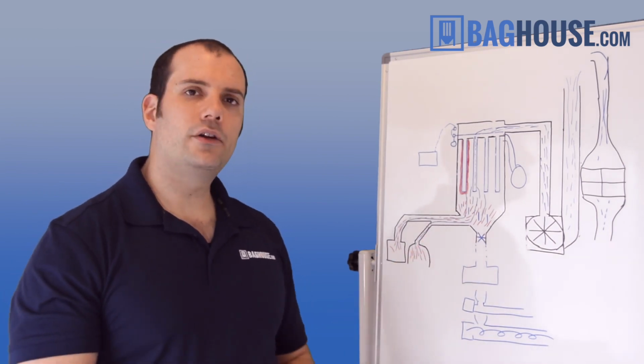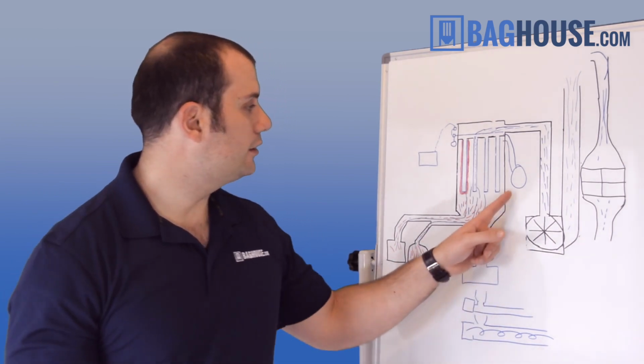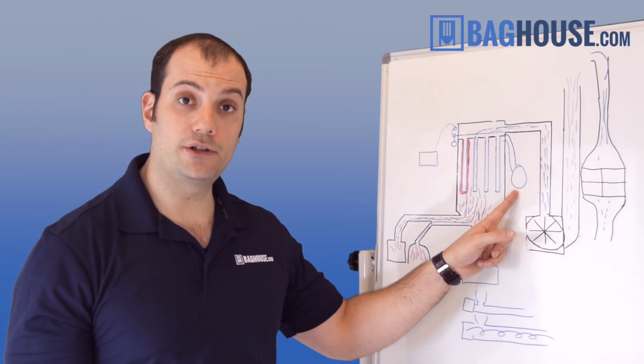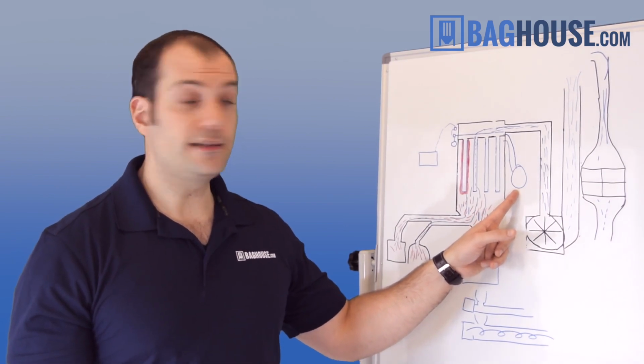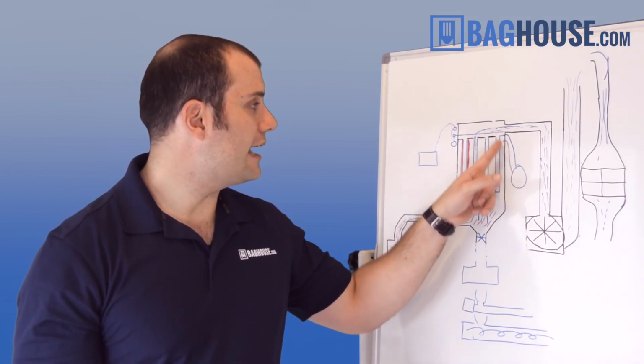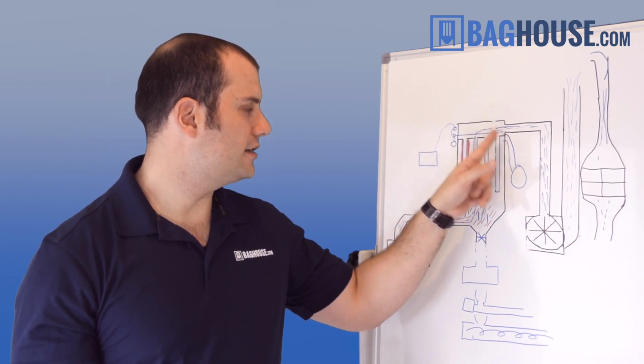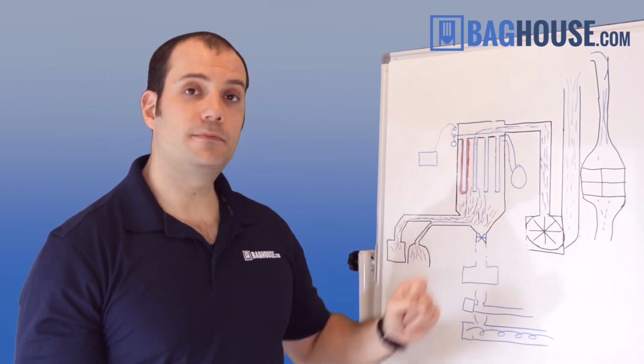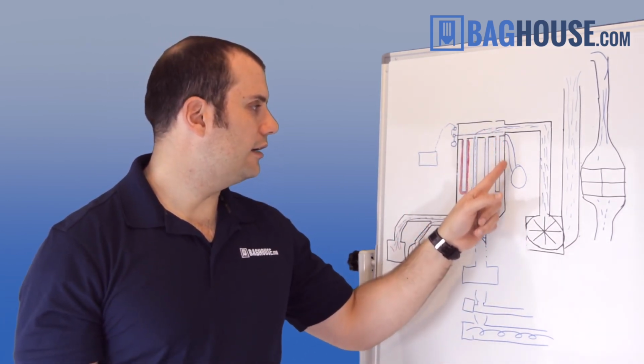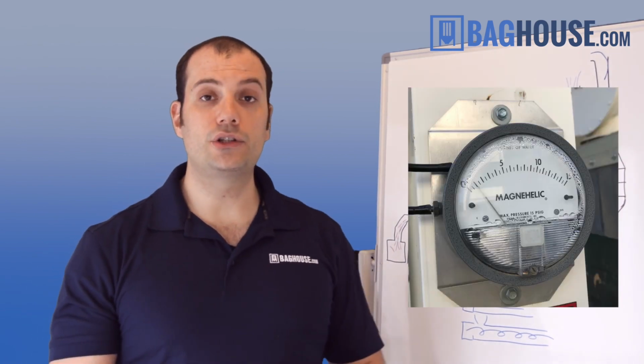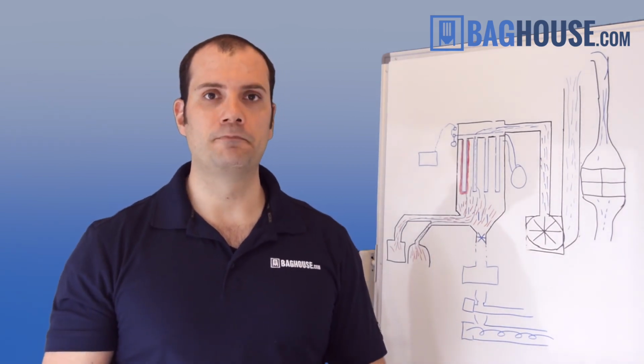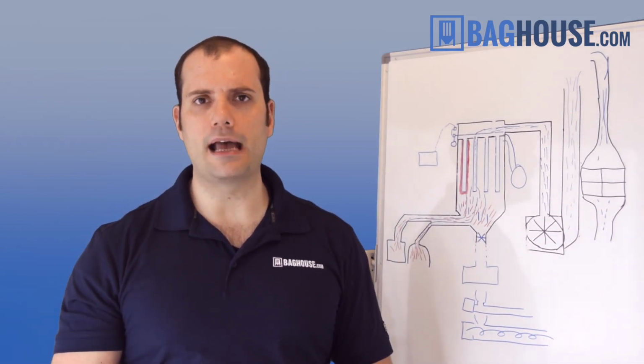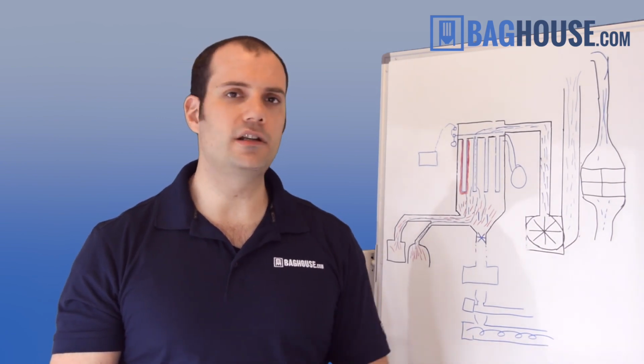But some of the smaller things you'll see on all Baghouses will include some sort of differential pressure gauge or monitoring device. And you'll see these two air taps here, one just above the tube sheet and one just below it. And these will be connected with air lines down to a gauge, usually a magnehelic gauge, or sometimes it's directly on a control board that can read differential pressure. This is the most important reading for your Baghouse operation, so it's always going to be present on any kind of dust collector you have.